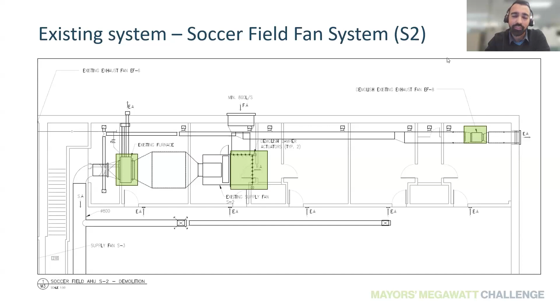We weren't able to connect this to the recovered heat from the ice plant, so instead we went with VRF technology. We have an air source heat pump connected to the DX coil there. Right now the plan is to just use this for heating, but if we ever need to, we can also use the same technology for cooling by using the reversing valve. The dampers, which were end of life, and also the insulation in the plenums needed a retrofit, so we did that. We installed new dampers, and as I mentioned, we replaced the exhaust fan with the ERV, so now that works for the exhaust of all the change rooms, and at the same time supplies preheated air to the fan system.